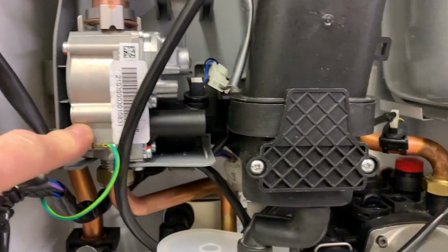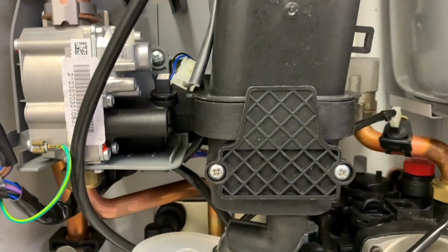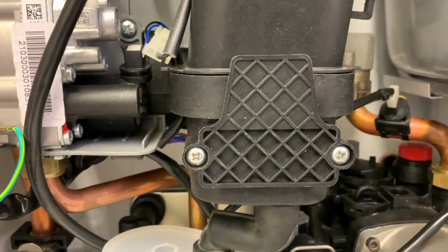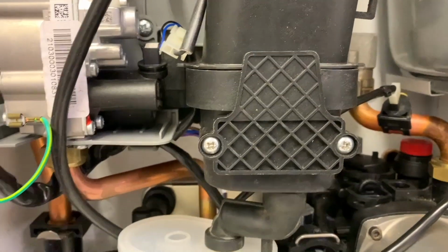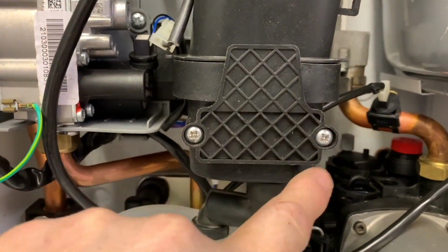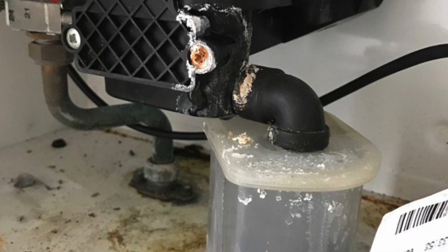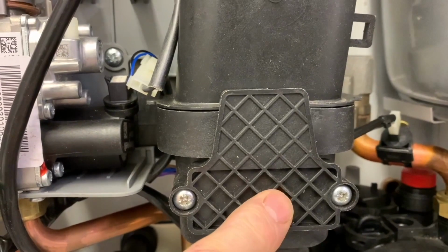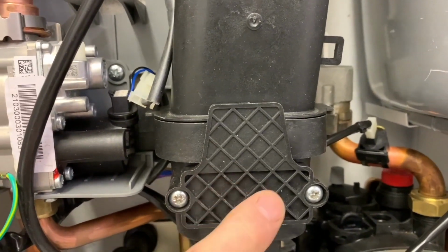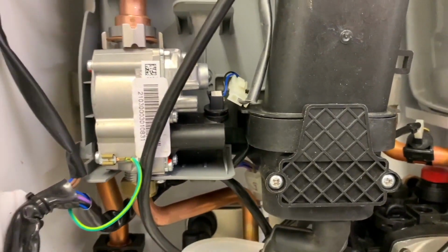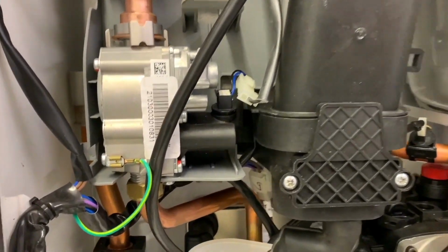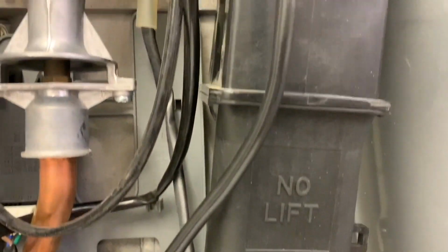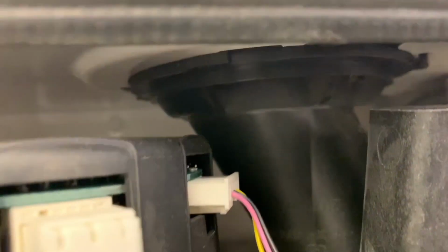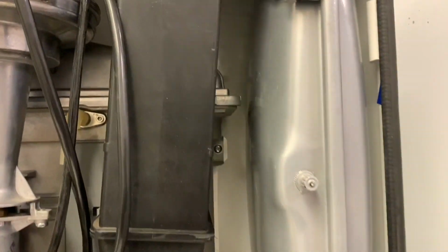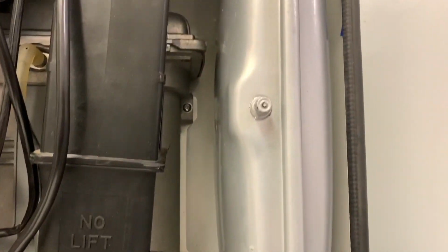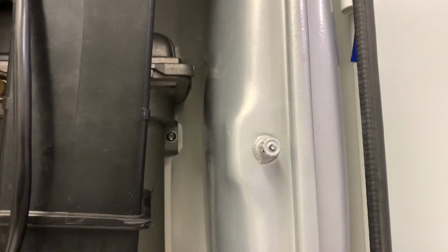Now the big plastic thing you can see here, this is the Achilles heel for the Logic and the Logic Plus in the older boilers. They're supposed to have sorted it out now. What we get is, if you open these up and you've got staining and you've got a load of water down at the bottom here, there's every chance this is cracked. Again, when we strip this boiler, I'll show you, but the sump on these is its Achilles heel. And you can see the plastic sump comes off, and then this is the flue system going off up to the turret. Just to the side is the expansion vessel, and we can get on the Schrader valve pretty easy.